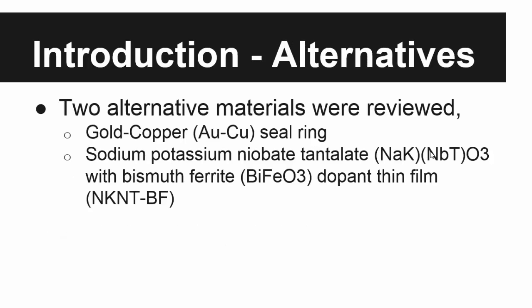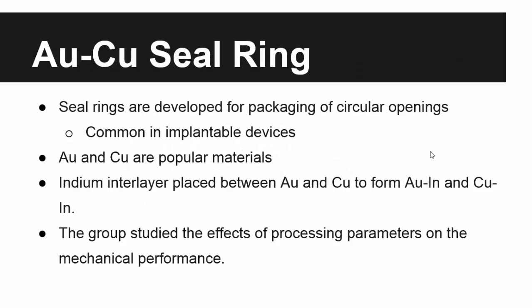And the two materials that we studied that has the potential to replace lead are gold-copper sealing with indium interlayer and sodium-potassium niobate tantalate. For short, it will be NKNT, with bismuth ferrite dopant as a thin film on piezoelectric material. And Minto is going to take over and talk a little bit about the gold-copper seal ring. So seal rings are used for packaging of circular openings that are usually found in MEMS devices. And they are mostly common in implantable devices because they are tubular or have circular input and output.